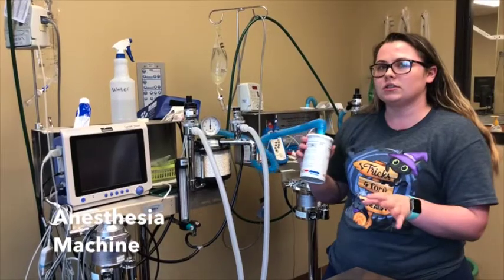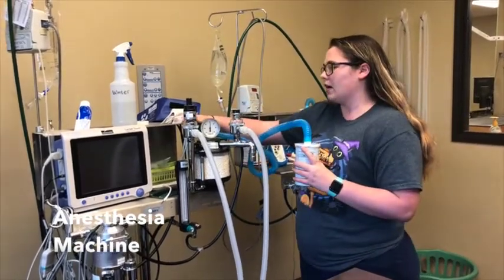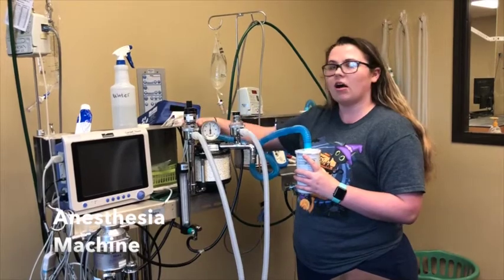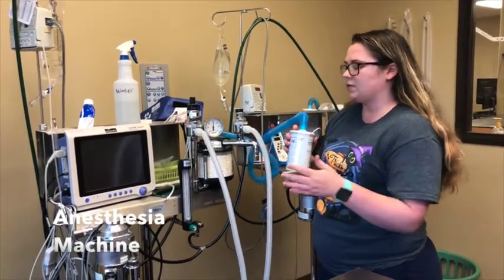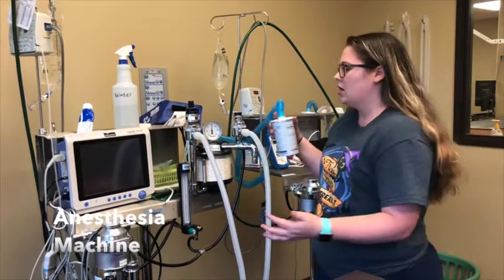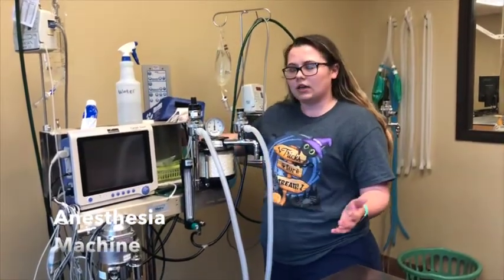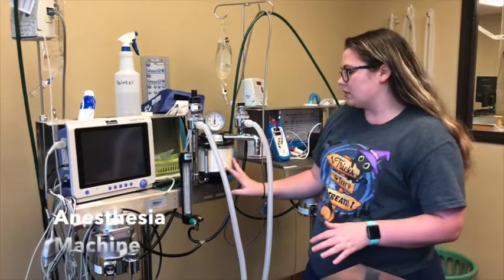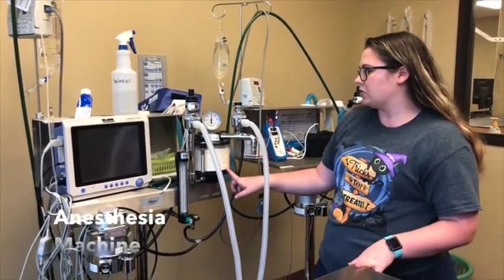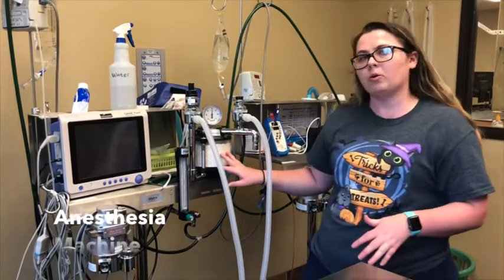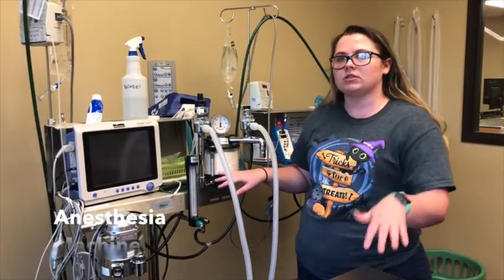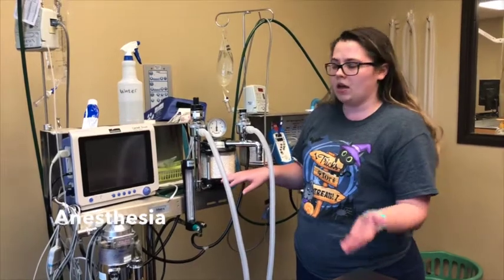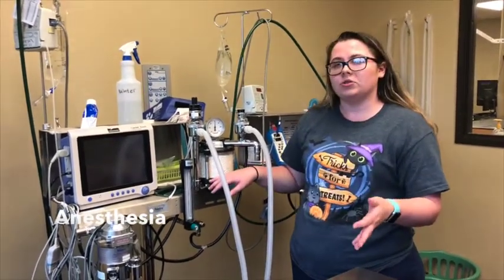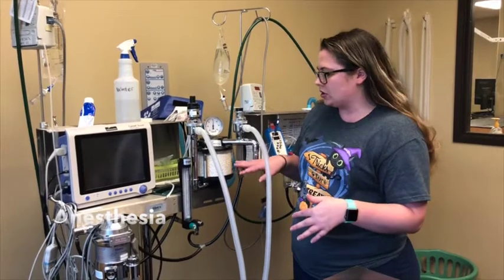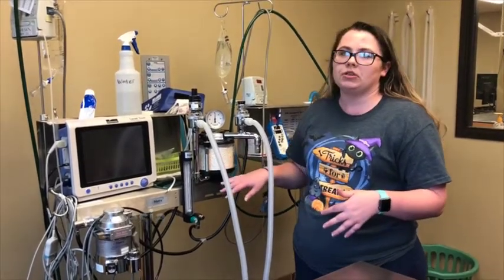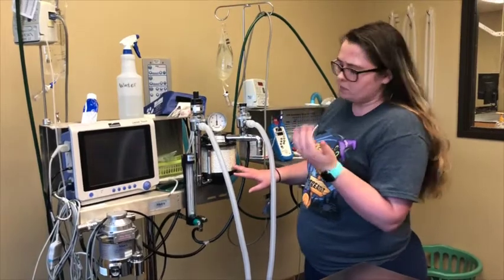This is our scavenging system. It's connected to the back of our pop-off valve. What this does is filter out the carbon dioxide that's going through and make sure no excess gas is getting anywhere. Our SodaZorb canisters right here are filled with our SodaZorb granules. These will actually turn purple when you need to change them. That just means it's absorbed too much carbon dioxide. It's normally about every 30 days when you need to start changing them. So after each surgery, you just need to look at it and make sure there's not a purple tint to it.